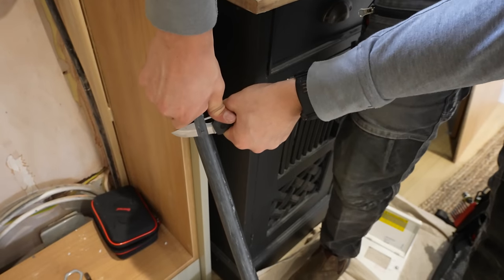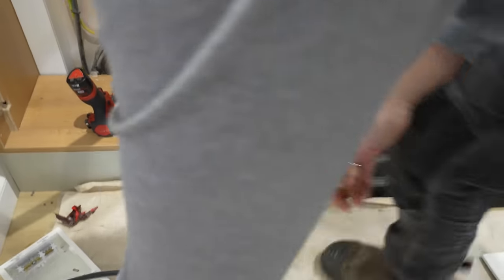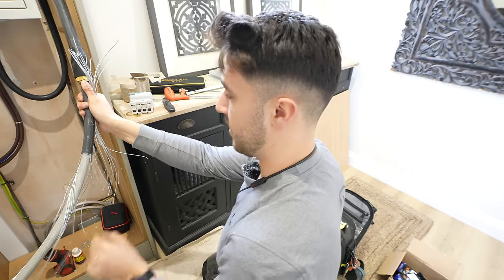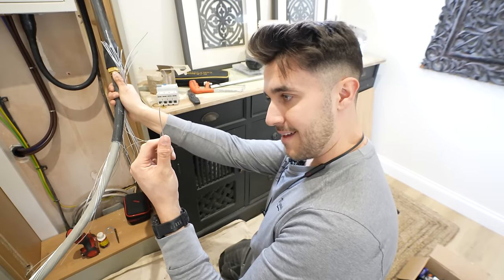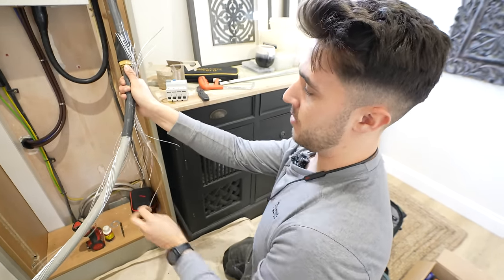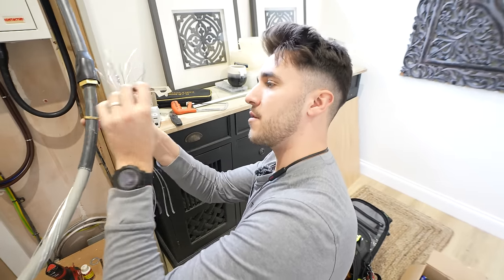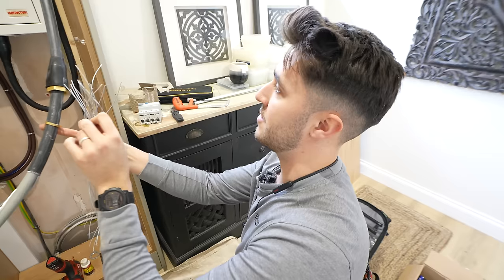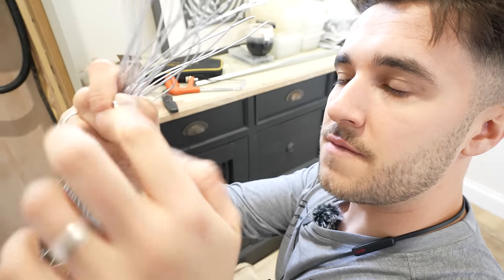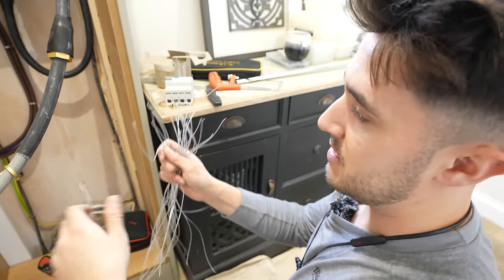Step three: strip the cable. Another little tip I got off the internet — when you first do your bend on the armoring, don't do a little gentle bend. You want to do a fast snap just to shock the metal. Take it by surprise. The reason being, it just comes off cleaner. If you do a slow bend, you see it forms the metal. Whereas if there's a nick in it already from the hacksaw and you just give it a quick snap, it just snaps the end off clean.